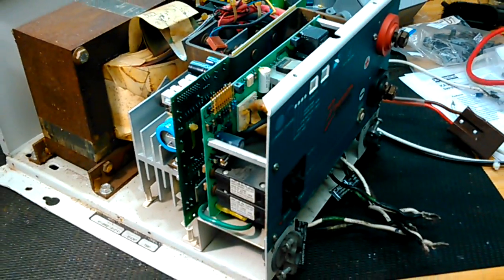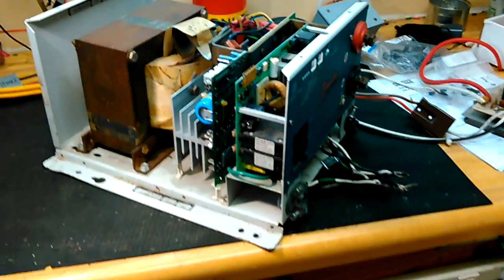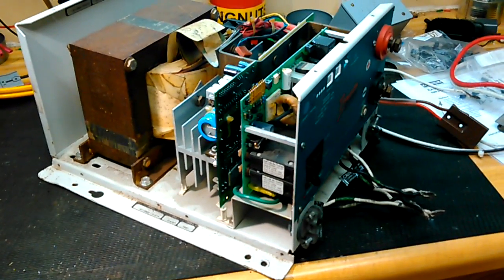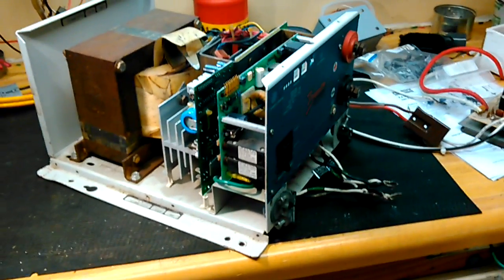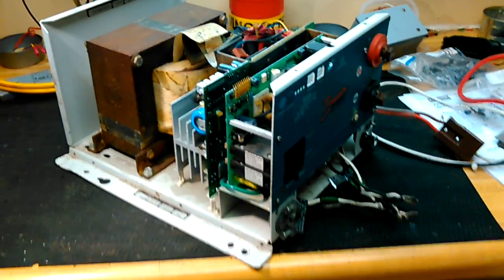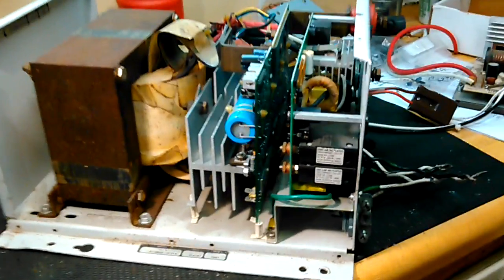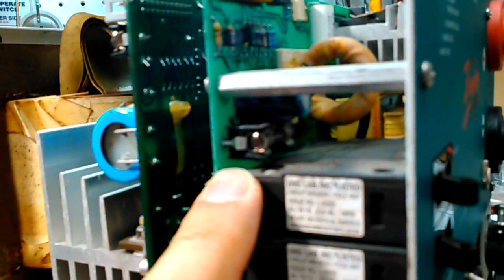Another thing I want to point out on the Xantrex Freedom 458: if you have some experience working with electronic devices and want to try to see what's wrong on your own, you can take the top of the unit off. There are 2 fuses in this unit - some only have 1. They're located one here on the inverter board, and one here - kind of hard to see - on the power board, the AC board. So some units have just 1, some have 2 fuses, and those are something you can check if the inverter stops working.